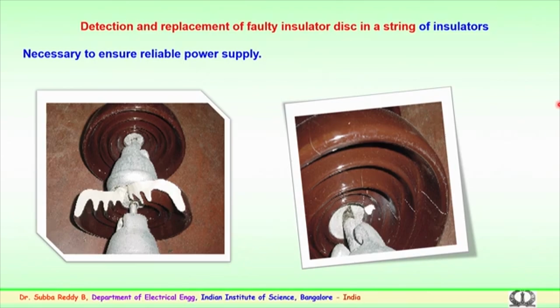So, what happens in case of faulty insulators? I also mentioned that in the insulator string, particularly in the transmission system, for a 220 kV system you have anywhere between 14 to 15 insulators, or 13 to 15 insulators in a string. For 400 kV it is 23 to 25 disc insulators. For 765 kV it could be 35 to 40 insulators, or depending upon the creepage, a larger creepage could be 29 to 30 insulators for 765 kV AC systems.